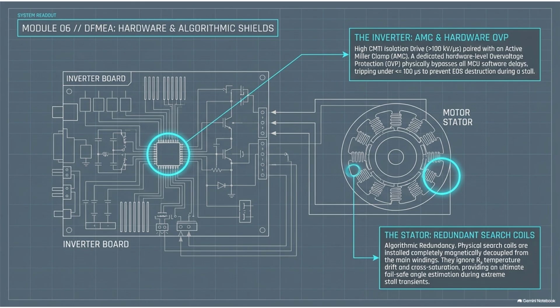Precisely. And the final major piece of the DFMEA blueprint defense goes all the way back to our very first root cause, the invisible EDM lightning destroying the bearings. Yeah. How do you defeat a microscopic electrical storm? Well, if it's lightning, you build a lightning rod. You build a microscopic lightning rod. The blueprints legally mandate the installation of high-conductivity carbon brush shaft grounding rings, or in some high-end applications, the use of hybrid ceramic bearings. Let's talk about the grounding rings first.